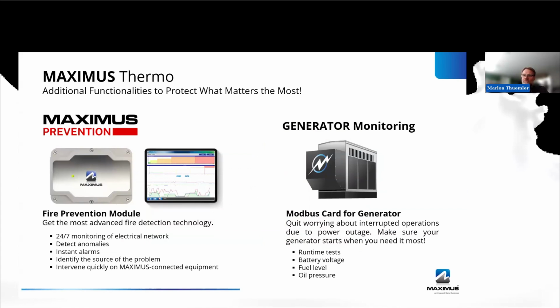A prevention module, electrical panel monitoring, and a generator monitoring card can be integrated into the MAXIMUS Thermo module. Did you know that faulty electrical equipment is one of the main causes of farm fires? More than 40% of building fires are of electrical origin. The MAXIMUS prevention system is an electrical monitoring device that detects anomalies by measuring amperage loss to earth and monitors temperature difference to prevent overheating of the electrical panel. You receive alarms in the event of irregularities. For quick evaluation, you have reports showing detailed monitoring.